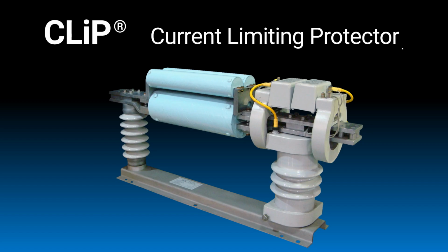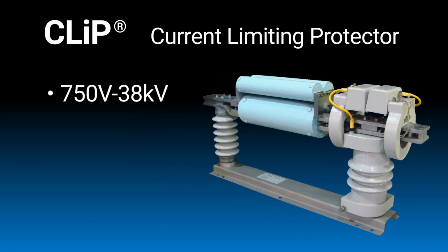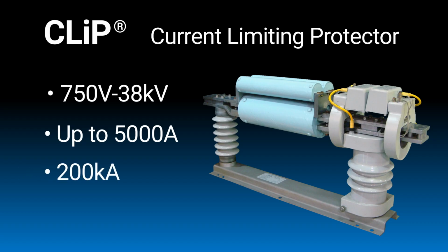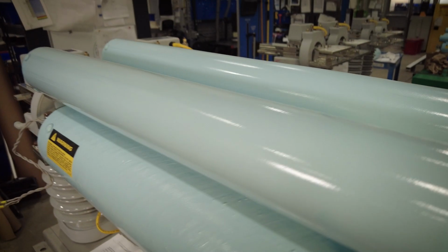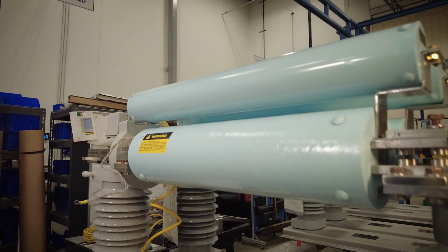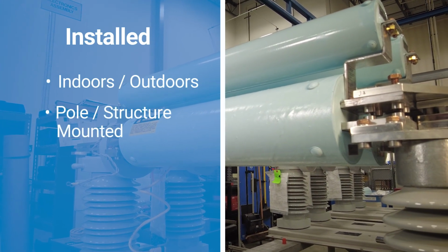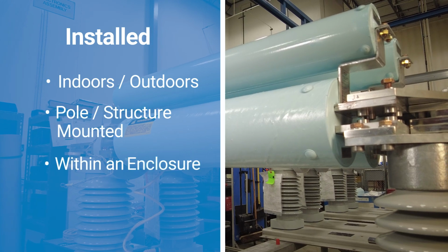At G&W Electric, we offer the CLiP current limiting protector that features the advantages of current limitation for 750 volt through 38 kilovolt systems with continuous current ratings up to 5,000 amps and short circuit ratings up to 200 kiloamps. Compact, totally sealed construction permits the CLiP current limiting protector to be installed both indoors and out, either pole or structure mounted or within an enclosure.